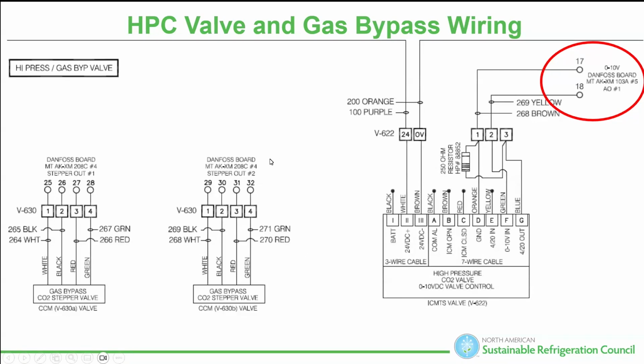All right, so I'm going to come here. This is the flash gas bypass valve. These are bipolar steppers. Real quick, I want to go through bipolar. A bipolar valve simply means, we all know how many steps, I don't care how many steps. I really never do care, because a step is a predetermined movement. When the controller, the iPro, whatever, sends a signal to it, it's a predetermined amount of movement on the rotors and the stators to move that valve positively or negatively, right? And so all a step means is the predetermined movement, unless I'm programming.